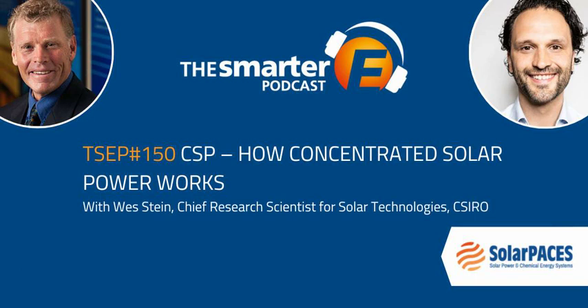That's exactly right, and that's the attraction of what we call two-tank molten salt, because the hot tank is always at the same temperature. So that, I guess, is one of the main benefits in contrast to PV. Are there any other differences or benefits in regard to general PV? Well, we have a lot more moving parts, of course. Photovoltaics don't have moving parts. So our operation and maintenance cost is generally a little bit higher, but the lifetime of these CSP systems can be up to 30 years. It's really only dictated by the materials that we choose to construct it with.